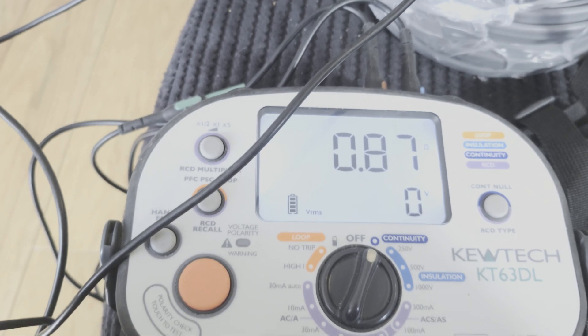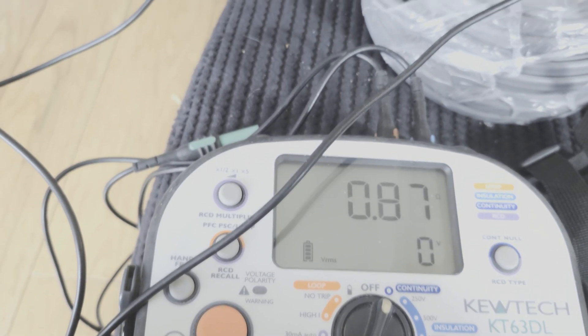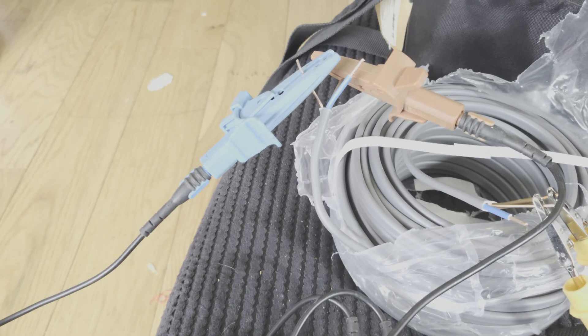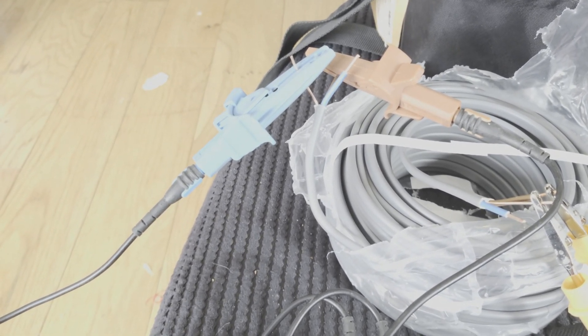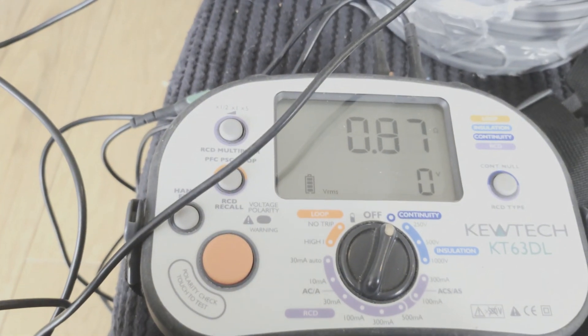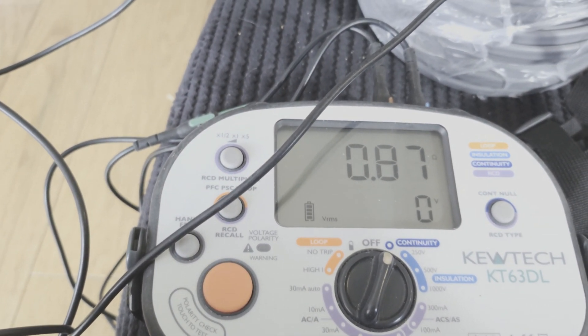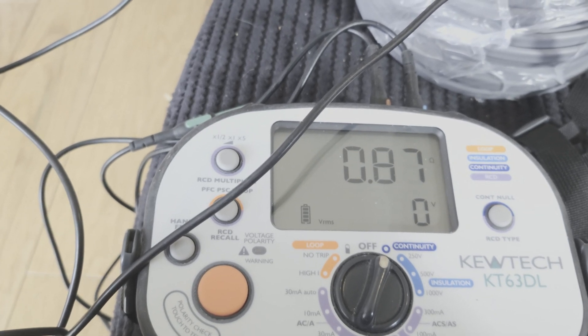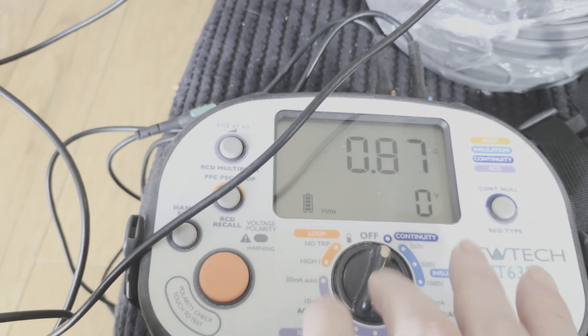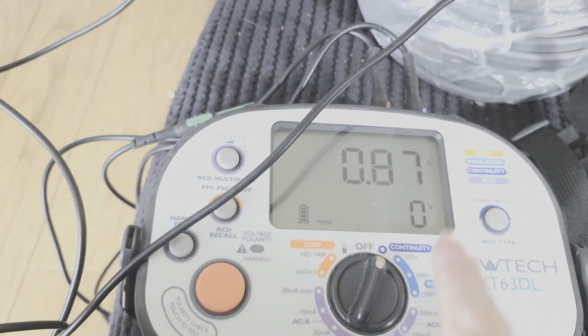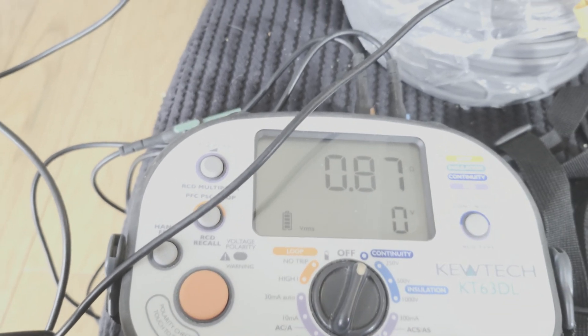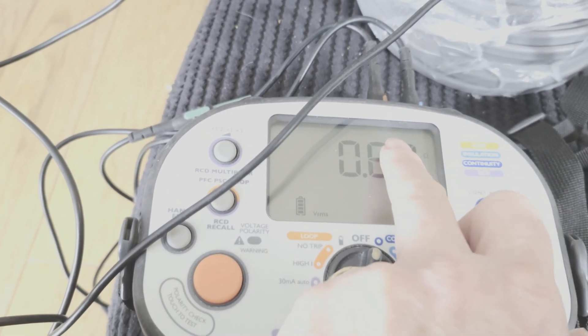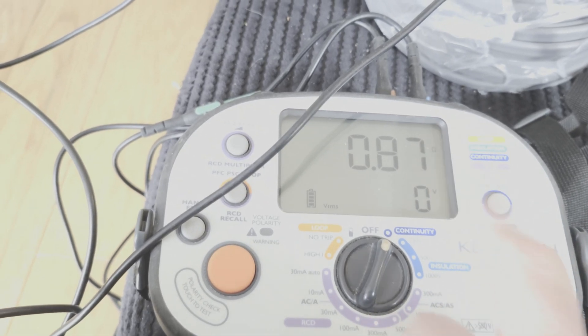So that's why you have to make sure that you null your leads. That's easy to do, but it's an easy mistake to make, and one I've made on a few occasions I must admit, and realized I've had to redo my tests because I didn't null my leads. At least with this tester it will tell you whether you've nulled them or not, because you will get the null at the top of the screen. If it's not there, you've not nulled your leads, so just check before you do the test that that null is written at the top.